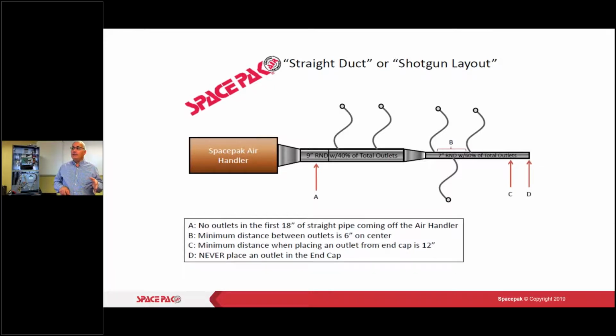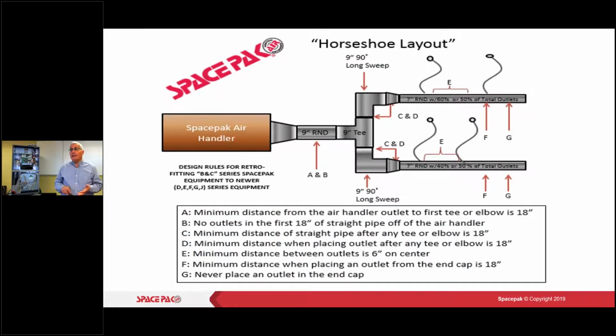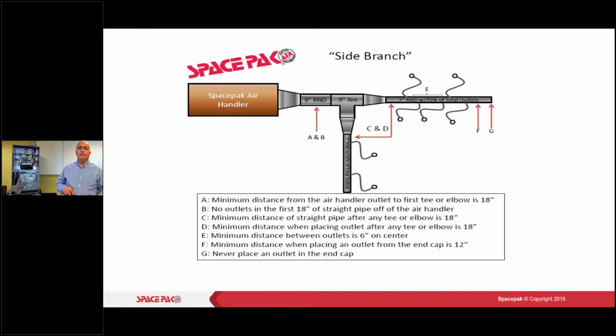Then what we're showing you here, I've got 40% of the outlets coming off, and then I can bring it down. But I don't see this working out well in a lot of jobs, and if it's older like this, generally that 7-inch plenum, if it was the fiberboard, has already started to break down. If we're going into a horseshoe outlet, again, I've got my minimum of 18 inches at 9-inch. That 9-inch T and the 9-inch elbows is what you're going to use, and then you would be breaking into that 7-inch plenum. Try to make it all 9-inch as best as possible. Side branch system, same thing, coming off of my air handler with that minimum 18 inches of 9-inch. The T's got to be 9-inch, and then we can break into the 7 inches there.